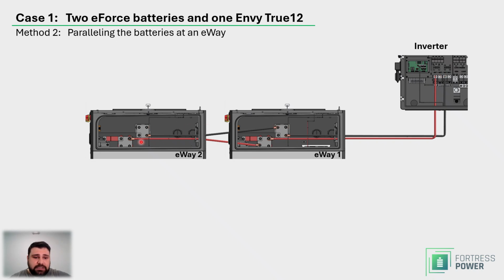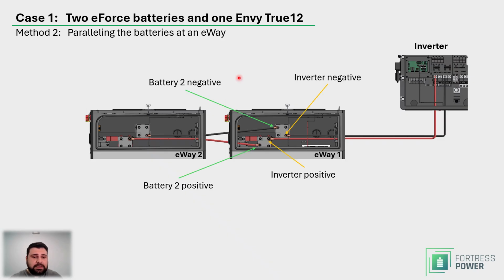But we have the bus bar to which eWay 2 is connected. Because you have the connection between eWay 2 and eWay 1, these bus bars serve as the combiner bus bars. So this bus bar combines the eWay 1 positive, for example, with the positive from eWay 2, i.e. all the positives of all the eForces that live under eWay 2, the positive of the inverter, DC positive, right here, and the positives of all the eForces underneath it. So this positive bus bar joins everything on the DC side, both on the inverter and the eWays. And the same is the story with eWay 1. So again, we parallel the batteries and we have battery 2 negative, battery 2 positive, inverter positive and inverter negative, which is great.